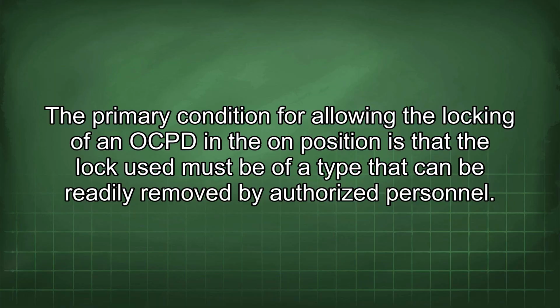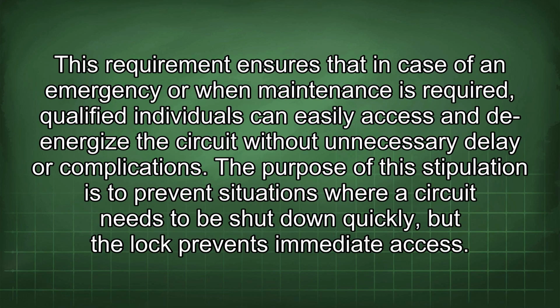The primary condition for allowing the locking of an OCPD in the on position is that the lock used must be of a type that can be readily removed by authorized personnel. This requirement ensures that, in case of an emergency or when maintenance is required, qualified individuals can easily access and de-energize the circuit without unnecessary delay or complications.